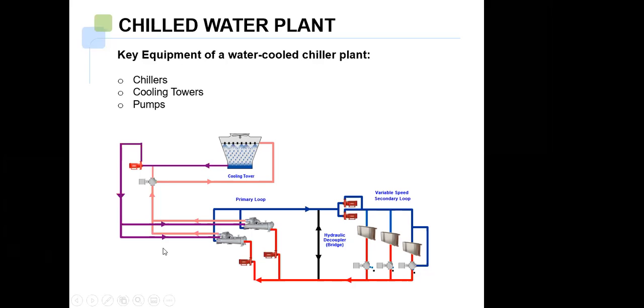So basically in this, if you are able to see my mouse, these are the chillers, which pick up the heat from the inside of the building through the air handling units, as we call them. It picks up the heat from the building, and this heat is transported through the water to this chiller, and then this chiller rejects the heat which has been accumulated from the building through these pumps to the atmosphere using a cooling tower.